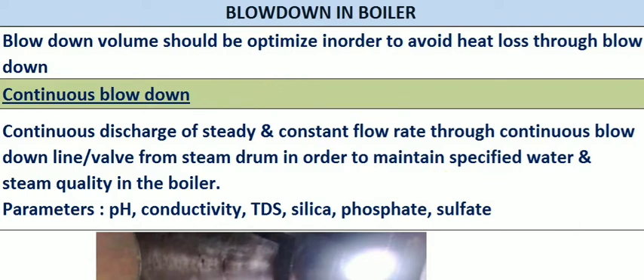There are two types of blowdown: continuous blowdown operation and intermittent blowdown operation. Continuous blowdown is a continuous discharge from the steam drum in order to maintain the specified water quality and steam quality in the boiler. The parameters we normally measure in the steam generator for steam and water are: pH, conductivity, TDS, silica, phosphate, and sulfate. These are the major parameters we need to monitor.